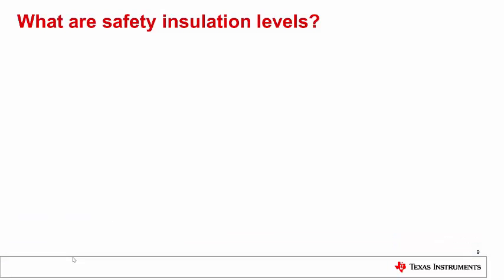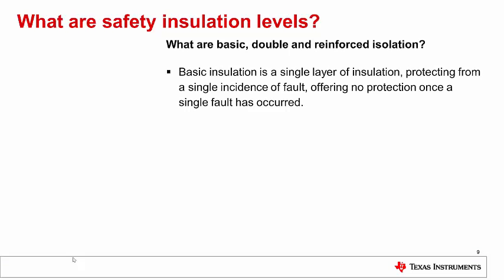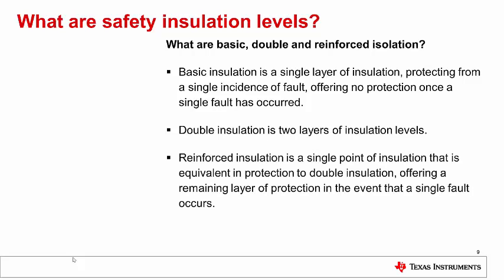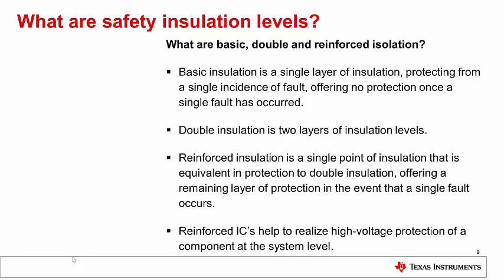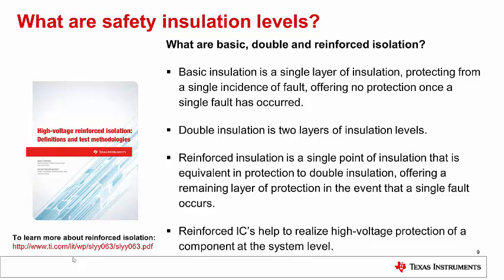Isolation terminology. What are safety insulation levels? Basic, double, and reinforced isolation. Basic insulation is a single layer of insulation protecting from a single incidence of fault, offering no protection once a single fault has occurred. Double insulation is two layers of insulation. Reinforced insulation is a single point of insulation equivalent in protection to double insulation, offering a remaining layer of protection in the event that a single fault occurs. Reinforced ICs help to realize high voltage protection of a component at the system level. To learn more, visit TI.com and look for the High Voltage Reinforced Isolation Definitions and Test Methodologies white paper, lit number SLYY063.